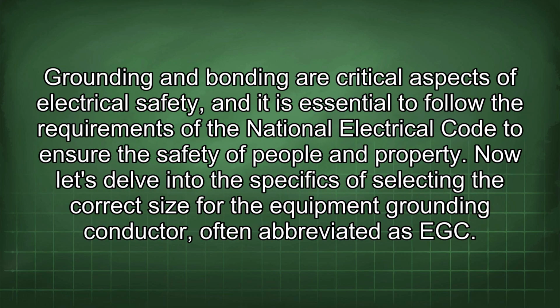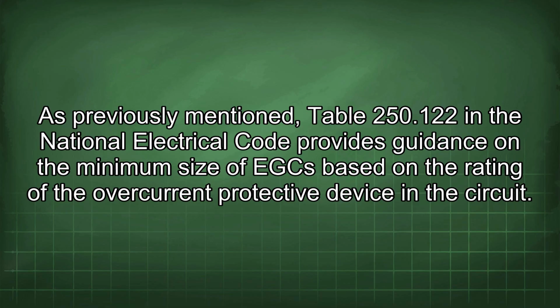Grounding and bonding are critical aspects of electrical safety, and it is essential to follow the requirements of the National Electrical Code to ensure the safety of people and property. Now let's delve into the specifics of selecting the correct size for the equipment grounding conductor, often abbreviated as EGC. As previously mentioned, Table 250.122 in the National Electrical Code provides guidance on the minimum size of EGC based on the rating of the overcurrent protective device in the circuit.